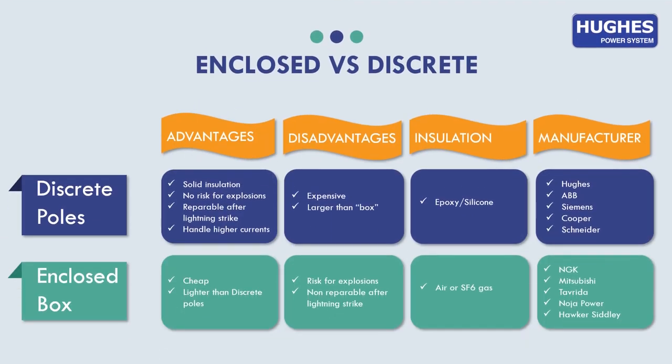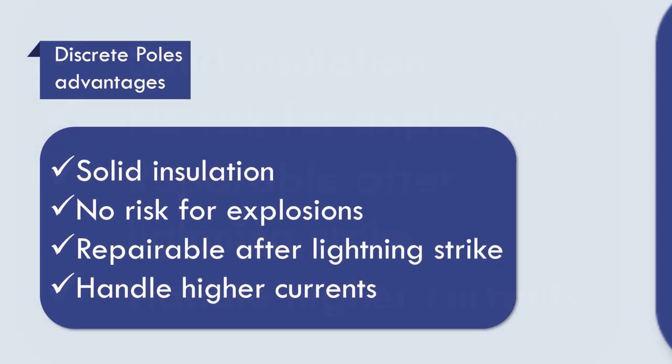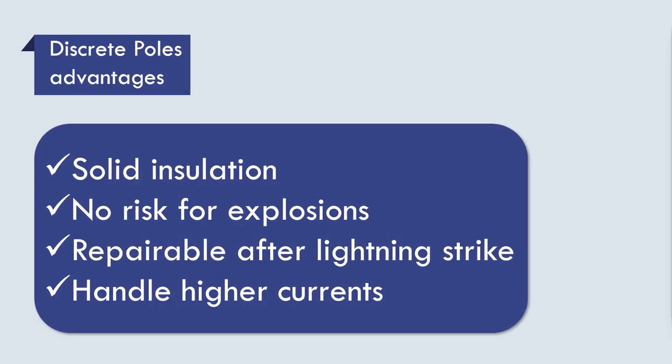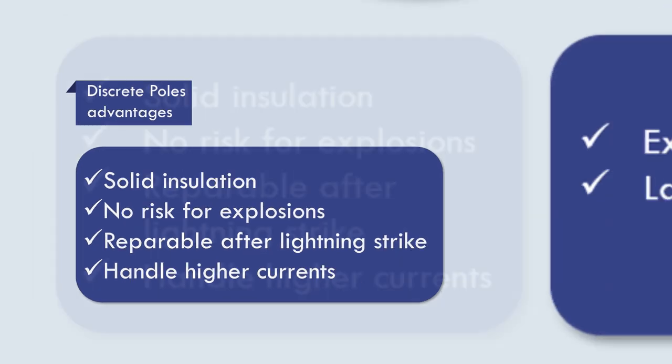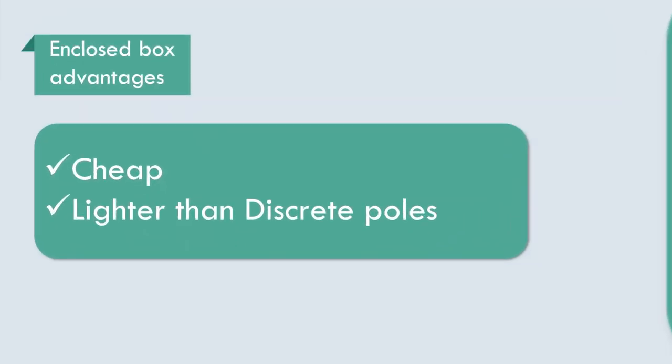Let's look at the comparison table for both types. First parameter is advantages of each type. Discrete poles' big advantage is that it is repairable or replaceable in case one of the poles is damaged. It has solid insulation, no risks for explosions, and can handle higher currents. Advantages of the enclosed box is that it is cheaper and lighter in weight.